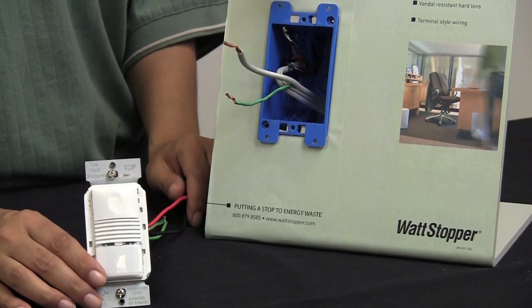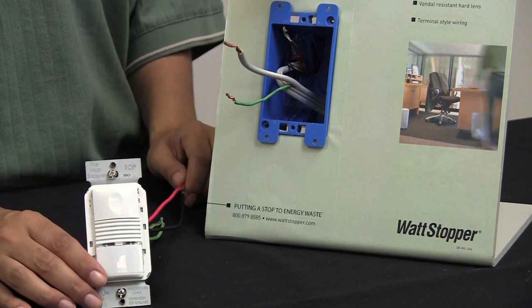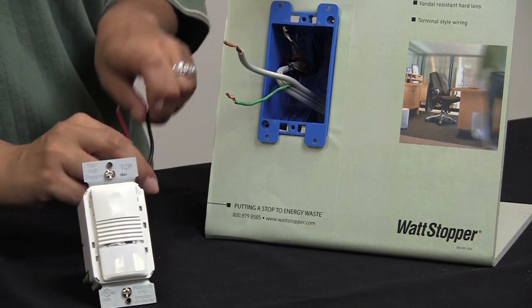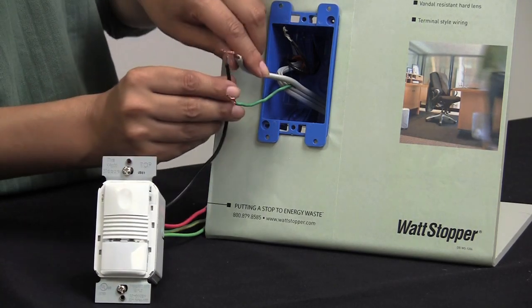So now we will wire up the PW100. Please be sure that all power is disconnected to the wall box before starting your wiring connections. First we will take the black wire from the sensor and wire that to our incoming hot.